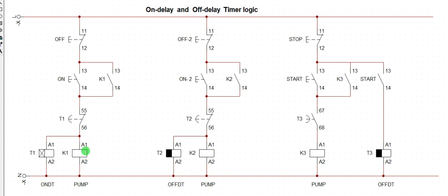So when this one is now latched, and I have T1 here for my on delay, once this one shuts the pump down, the entire system will also shut down, because this pump is what I use to latch. And once the latch is no longer there, the timer itself will get disengaged. The power to the timer will be cut off. The power to the contactor will also be cut off. So what is returning the signal here is my latch.